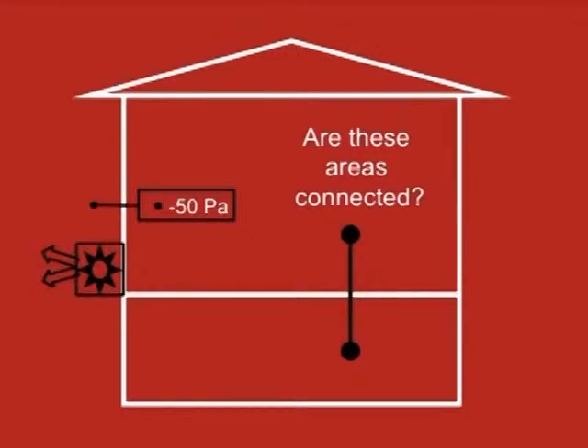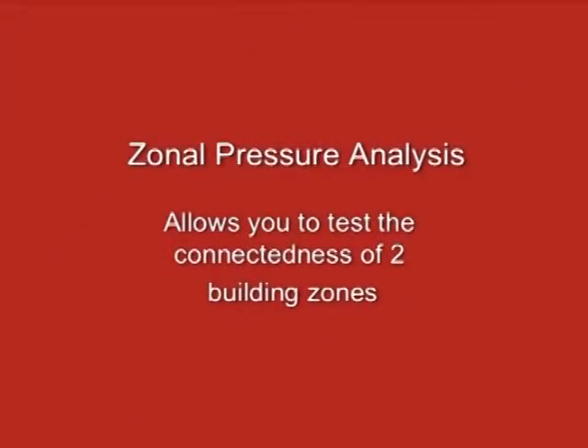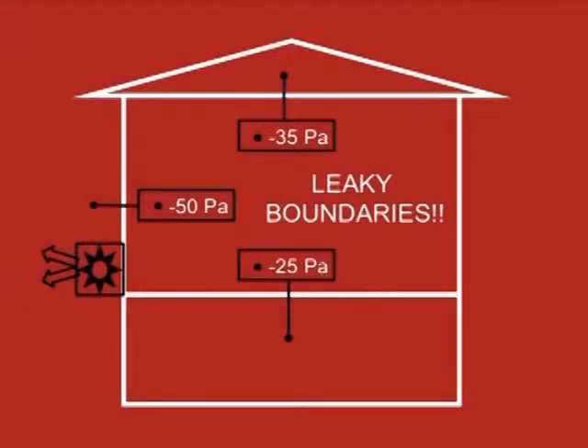This test determines the degree of connectedness between two zones of a building. If we record a value between 0 and 50 pascals during zonal pressure analysis, then the boundary between the two zones is a leaky one.